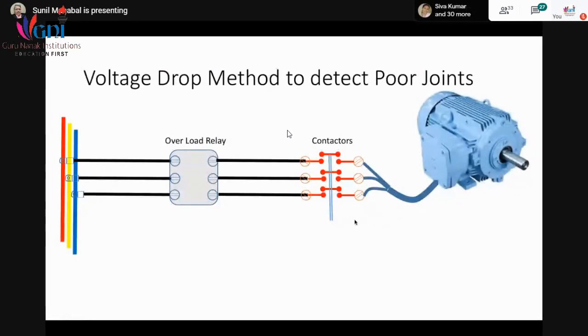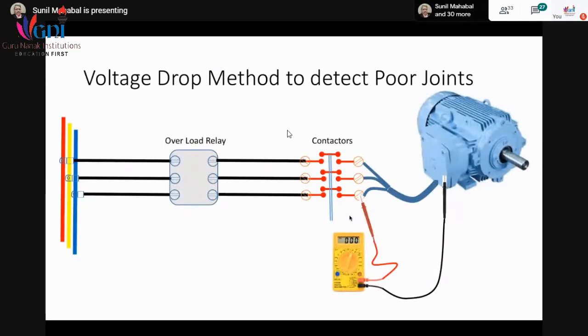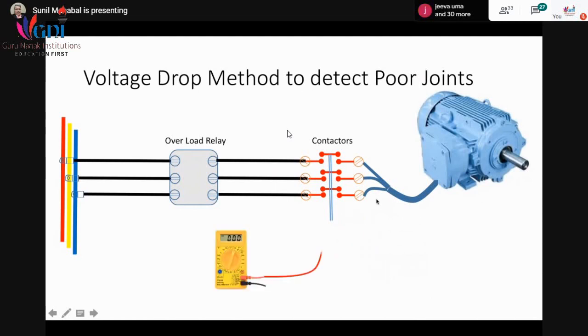Now how I checked it with the multimeter: suppose we take this blue phase, then from the contactor it reaches the motor. Is there any voltage drop in this wire? Same phase, I am not talking about different phases. Is there any voltage drop in this connection? No. Then is there any voltage drop across the contactor? Because of sparking and all, the moving contact might have become bad and developed carbon, which can be a reason for bad contact. So is there any voltage drop here? There also I could not find any voltage drop.